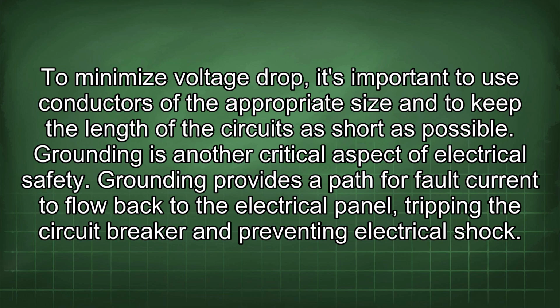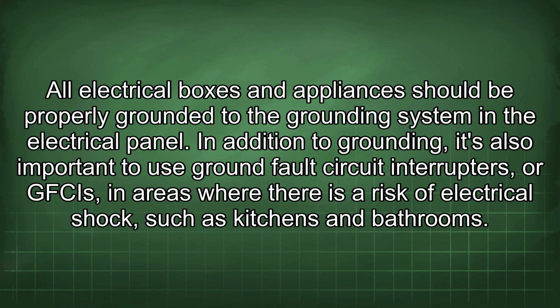Grounding is another critical aspect of electrical safety. Grounding provides a path for fault current to flow back to the electrical panel, tripping the circuit breaker and preventing electrical shock. All electrical boxes and appliances should be properly grounded to the grounding system in the electrical panel.